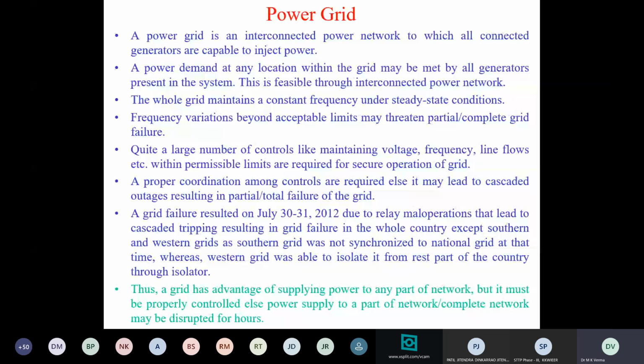Why was the southern region not disturbed? Because at that time the southern region was not connected to the national grid. And the western region, although it was connected to the national grid, before something happened, isolated itself from the main grid and protected itself. So that means the grid has the advantage of supplying power to any part of the network, but it must be properly controlled. If it is not properly controlled, part of the network or the complete network may be destroyed, and that will endanger the security of the grid.